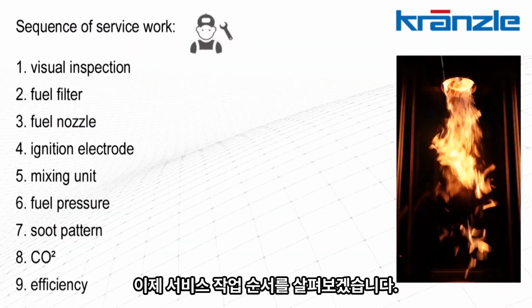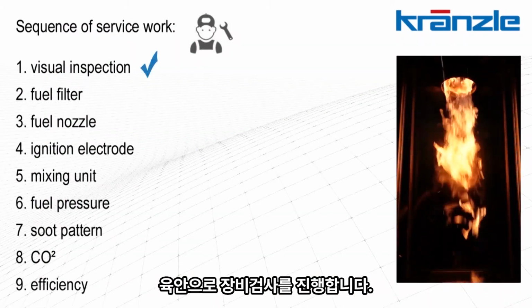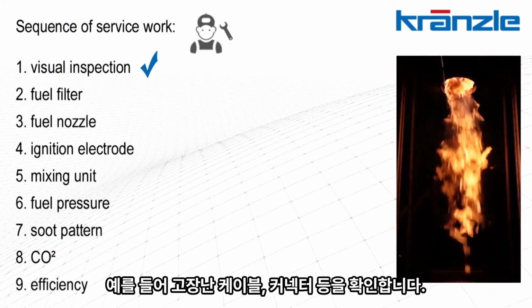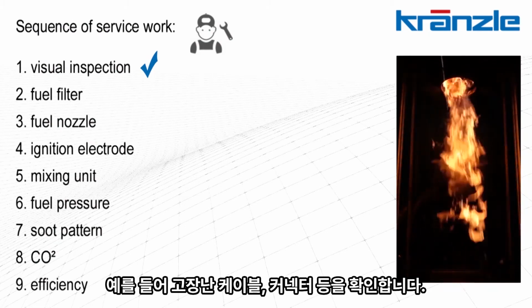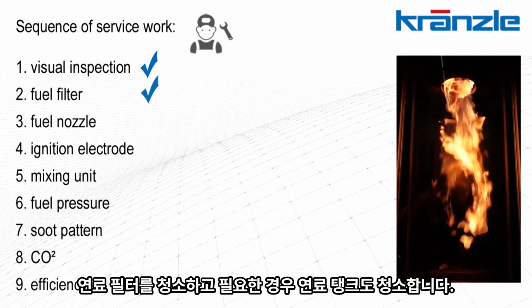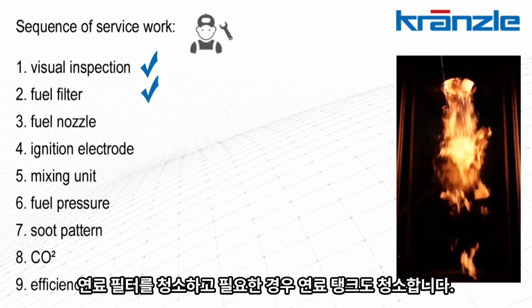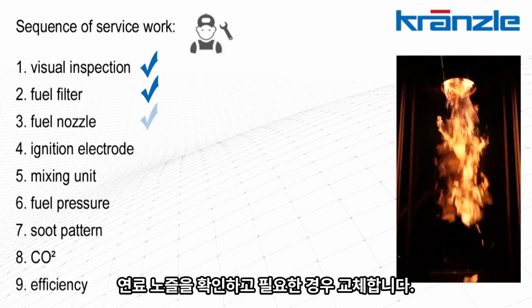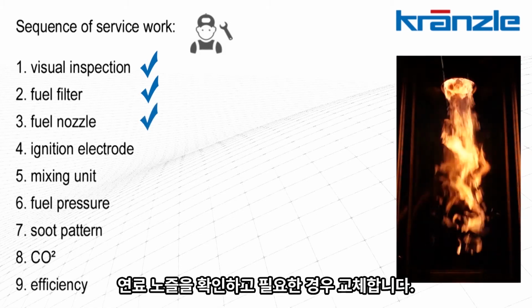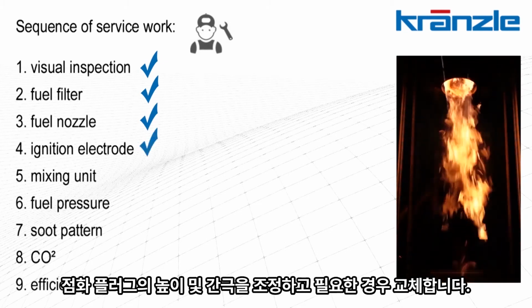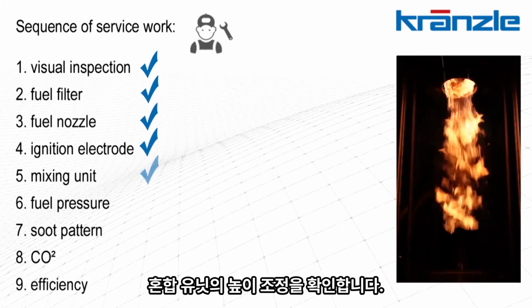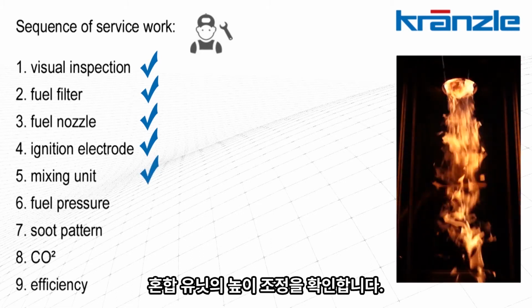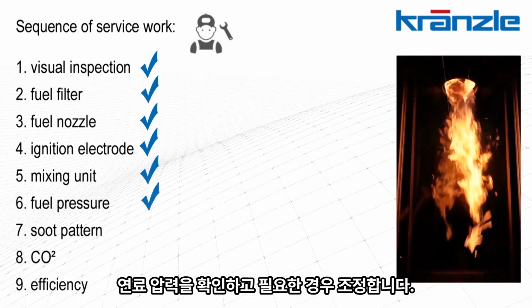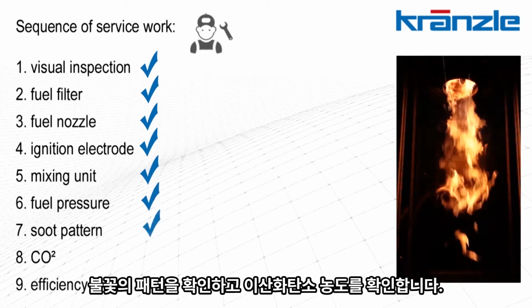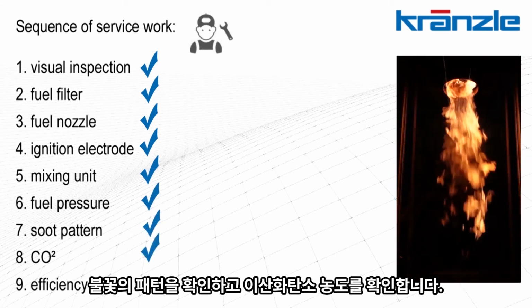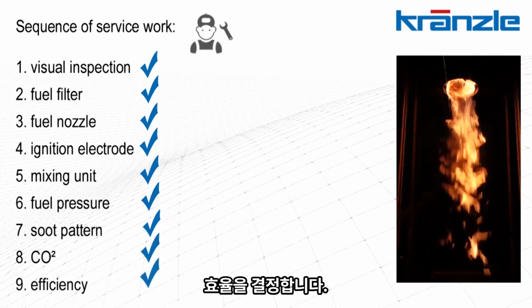Let's look at the sequence of service work. Visual inspection regarding the general condition of the device, for example, defective cables, connectors, and so on. Then clean the fuel filter and, if necessary, also the fuel tank. Check the fuel nozzle and replace if necessary. Adjust the ignition electrode and replace if necessary. Check the height adjustment of the mixing unit. Check the fuel pressure and adjust if necessary. Check the soot pattern, check the CO2 levels, and determine efficiency.